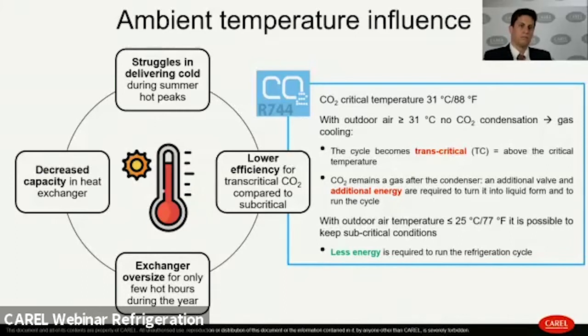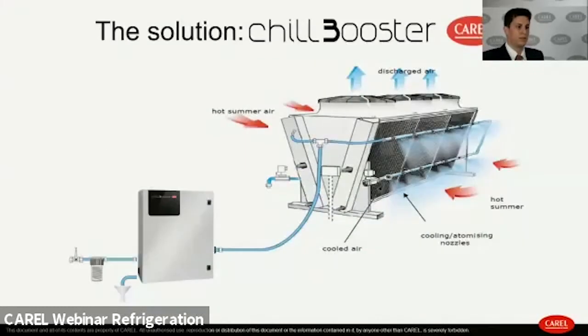So we can now jump into CAREL's solution to mitigate heat peaks and to restore cooling capacity and reliability of the system. CAREL's proposal is chillBooster. chillBooster is a system composed of a pumping station and a distribution system that has to be installed on the heat exchanger, gas cooler, chiller, whatever it is. The distribution system sprays water through nozzles, and water is evaporated by extracting heat from the air. Thus, the temperature of the air decreases, and it is able to extract more heat from the heat exchanger. So the cooling capacity is restored to the design condition.